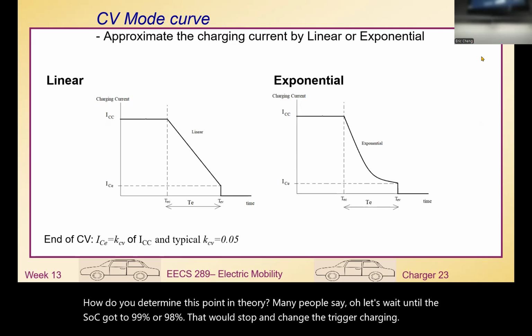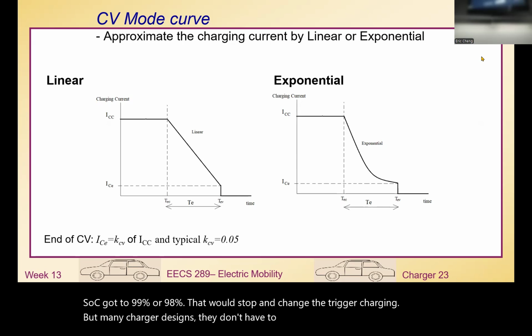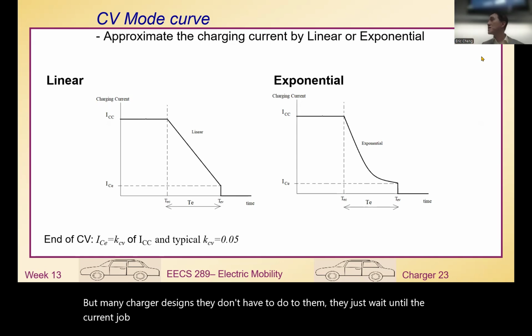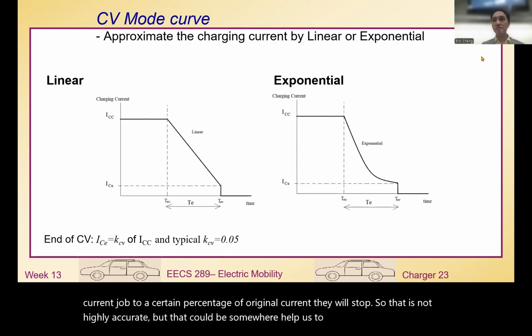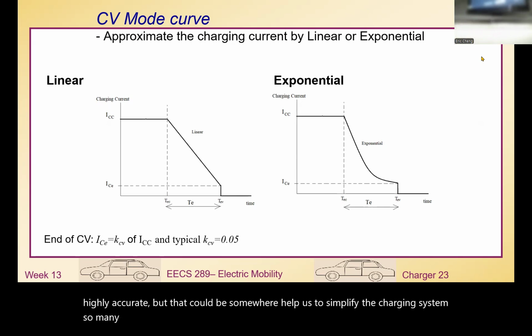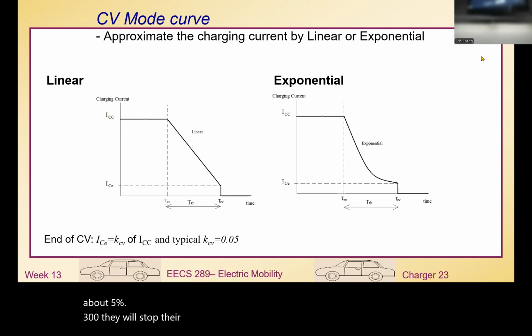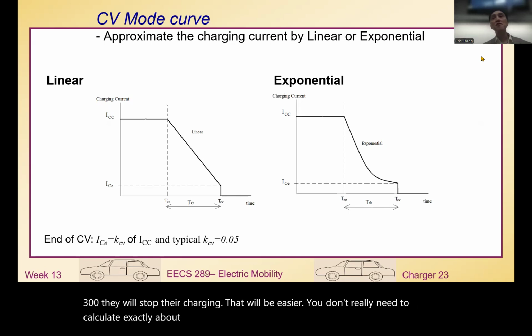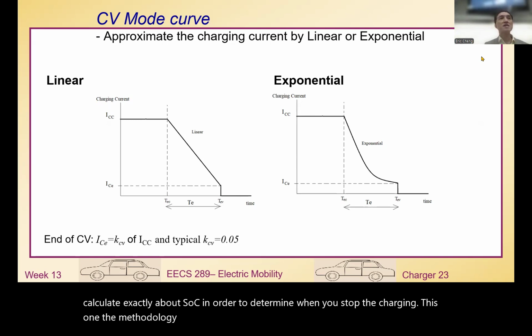But many charger designs don't have to do that - they just wait until the current drops to a certain percentage of the original current, then they stop. That's not highly accurate, but it helps simplify the charging system. So many charger designs will wait until it drops to a constant factor of about 5%, then stop the charging - that's easy enough. You don't really need to calculate the exact SOC in order to determine when to stop charging. This is one of the methodologies many designs have been using.